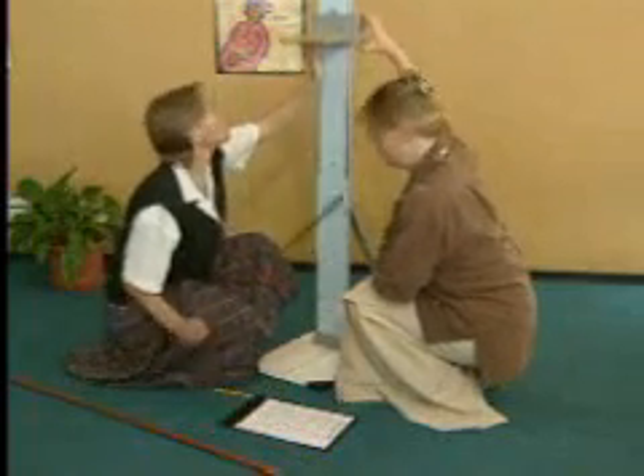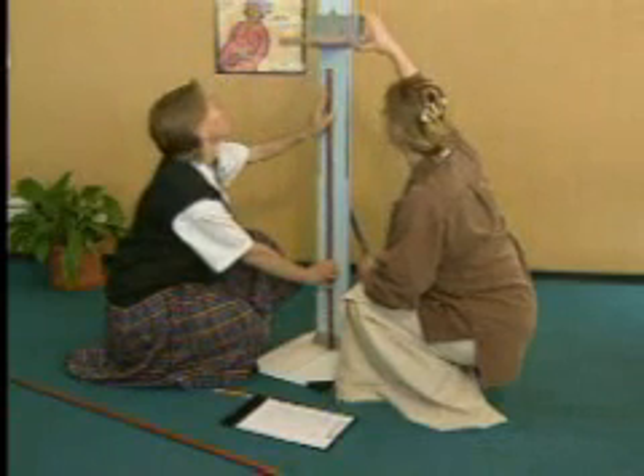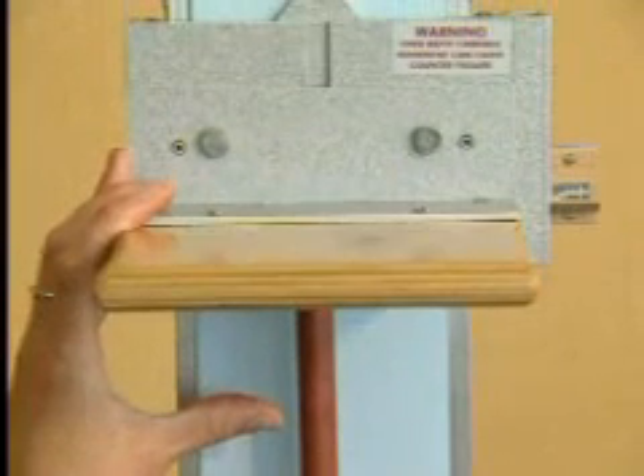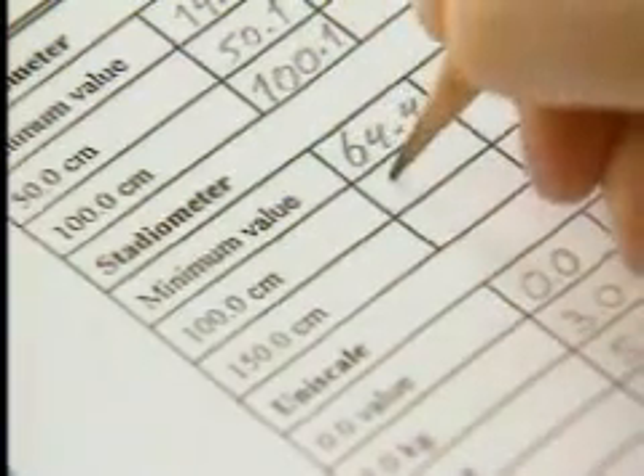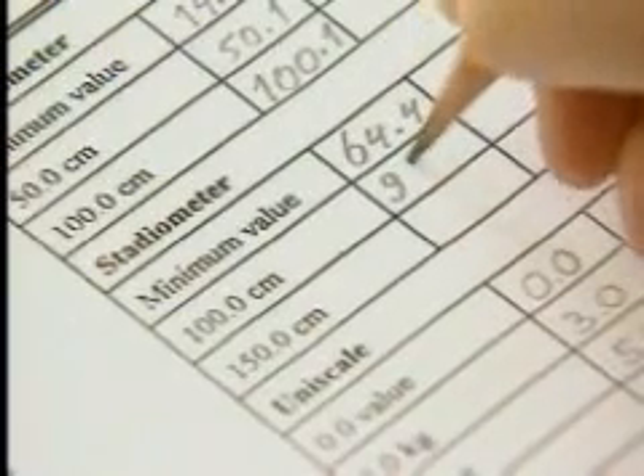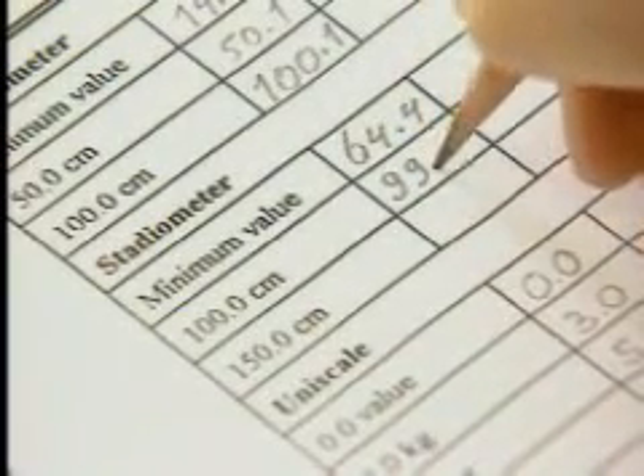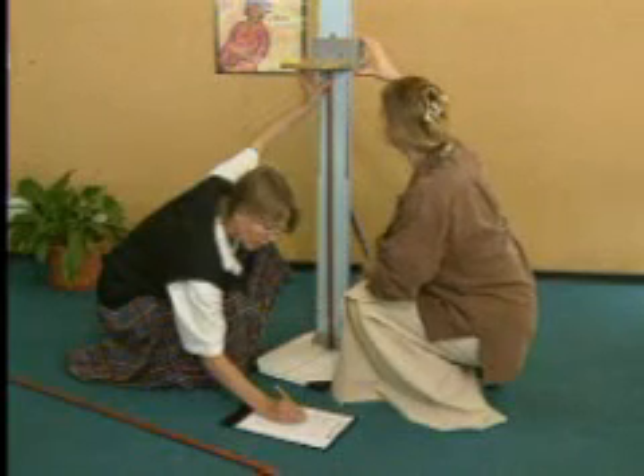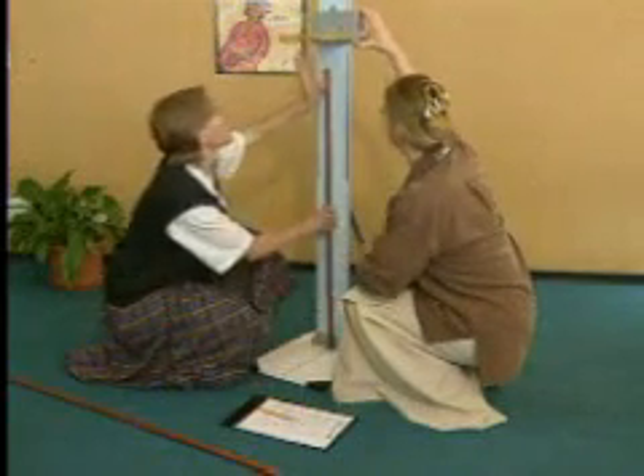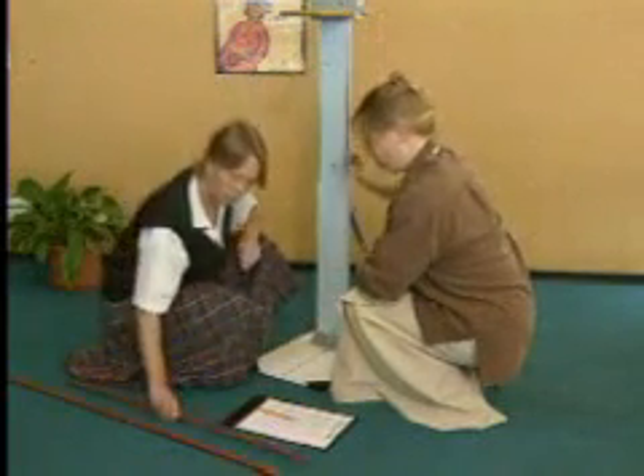Then, stand a calibration rod of known length on the flat base of the stadiometer. Bring the headboard squarely over this rod and record the reading on the calibration form. This process is repeated with each different length of calibration rod, and the reading is recorded. If there is a disagreement at any of the known lengths, bring it to the attention of the supervisor.